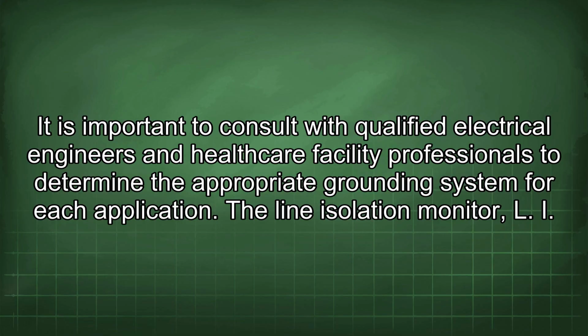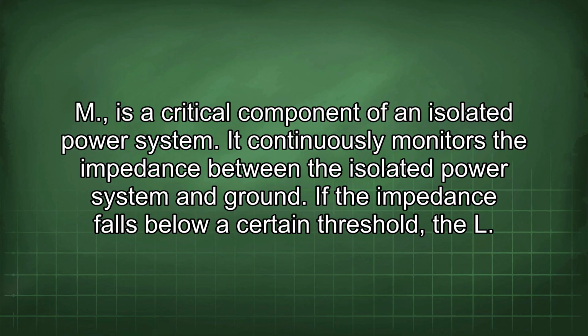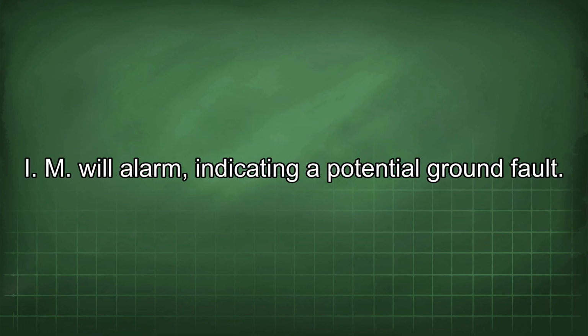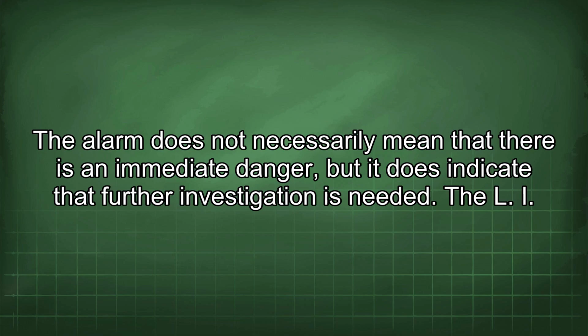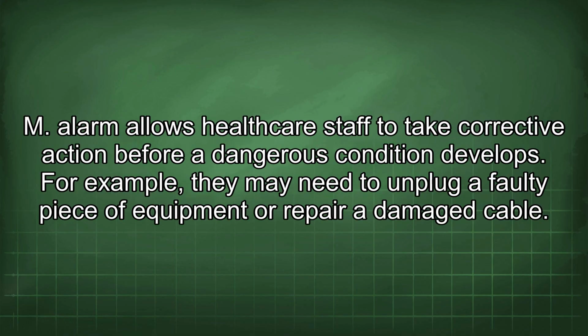each application. The line isolation monitor, LIM, is a critical component of an isolated power system. It continuously monitors the impedance between the isolated power system and ground. If the impedance falls below a certain threshold, the LIM will alarm, indicating a potential ground fault. The alarm does not necessarily mean that there is an immediate danger, but it does indicate that further investigation is needed. The LIM alarm allows healthcare staff to take corrective action before a dangerous condition develops. For example, they may need to unplug a faulty piece of equipment or repair a damaged cable.